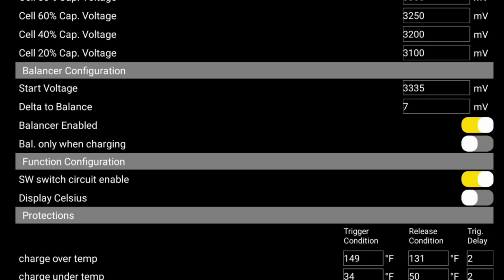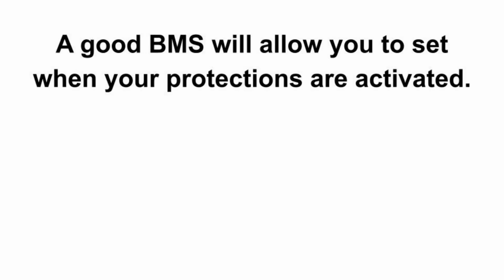With this BMS, you are able to configure the balancer configuration. You can turn balancing on or off, and whether to balance when charging only. You can set the voltage of the cell, which will turn on balancing if any of the cells reach that voltage, and if the difference between the lowest and highest cells is more than the amount you enter in the delta to balance field. A good BMS will allow you to set when your protections are activated.